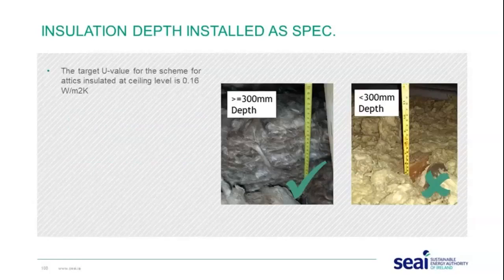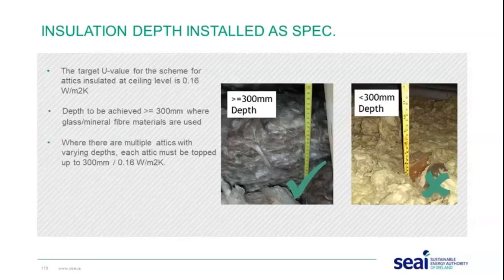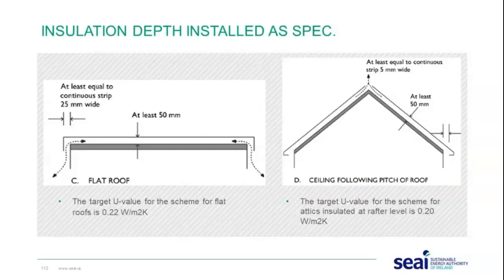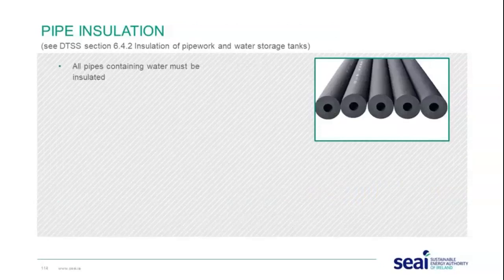The target U-value for scheme attics at ceiling level is 0.16, and the depth required is 300 millimetres when using mineral fibre. Where there are multiple attics with varying depths, each attic must be topped up to 300 millimetres to achieve around 0.16. For a flat roof, the target U-value is 0.22, and for ceiling-followed insulation where the ceiling follows the pitch of the roof, the target is 0.20.